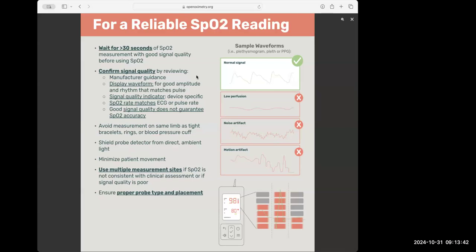You raised an interesting question: do all devices have alarms? Certainly the finger probes and finger clips don't. But they have signal quality indicators, as you know, Sandy. Mike raised the specter of alarms, and I don't know what the expectation is. Clinicians using these things might think there is an alarm, and maybe they should be alerted to the fact that there might not be. I think that's a good point about signal quality.